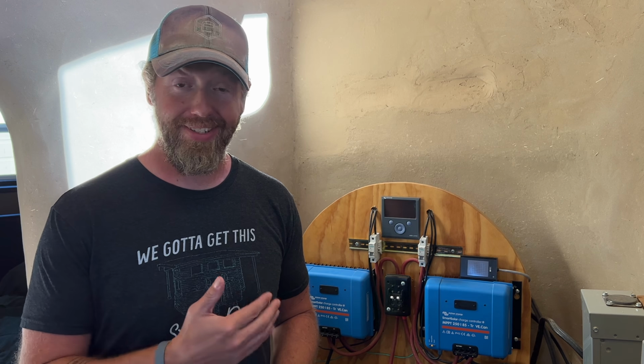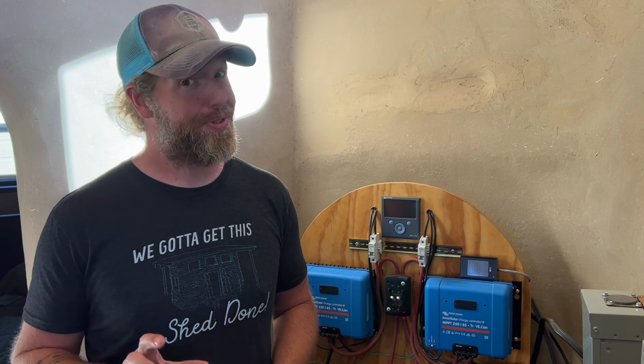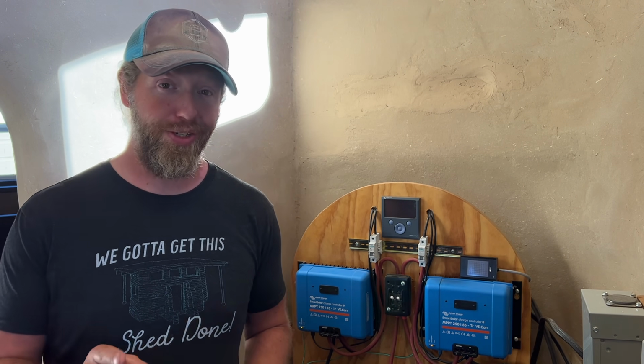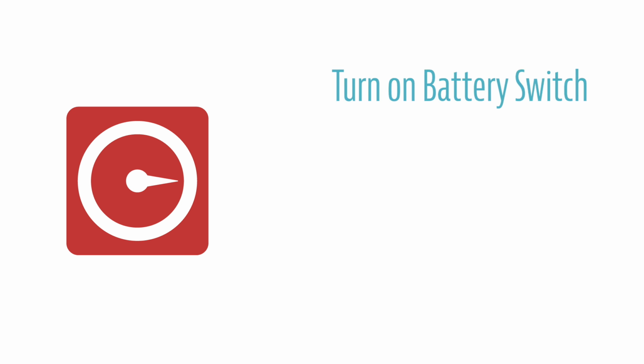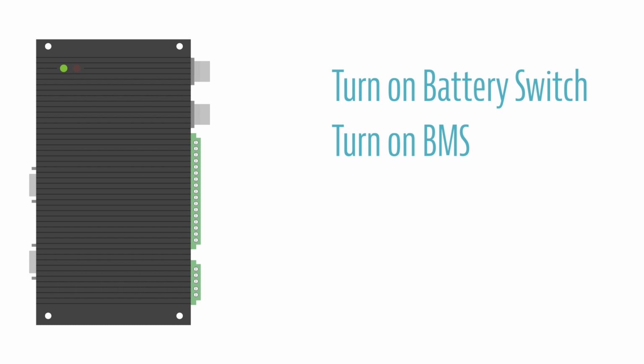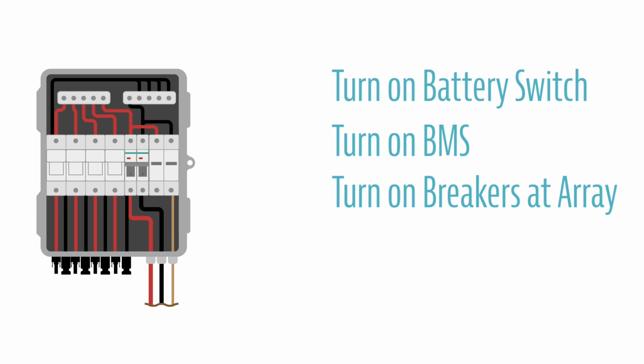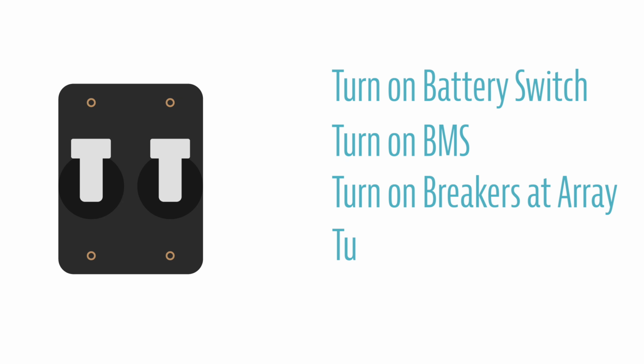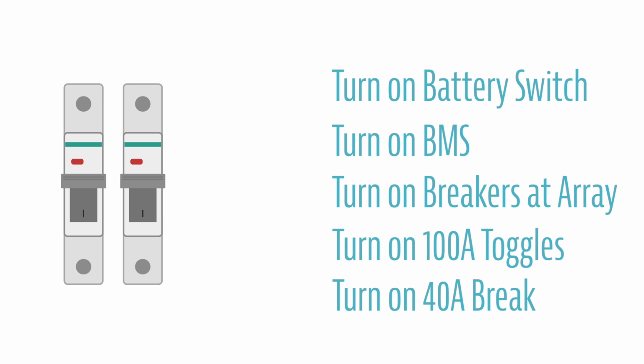Once all your panels are connected and all your wires are run inside, it's time to boot up the system with solar power for the first time. Here's the order: 1, turn on the battery disconnect switch. 2, turn on the BMS and wait for the contactor to turn on. 3, flip on the breakers in the combiner boxes at the solar panel ground mount. 4, turn on the 100 amp pole toggle switches going from the MPPT charge controllers to the system. 5, turn on the 40 amp circuit breakers going from the solar panel array to the MPPT charge controllers.